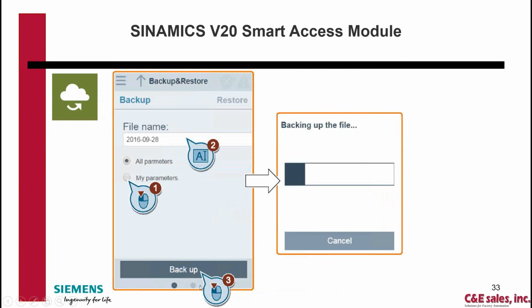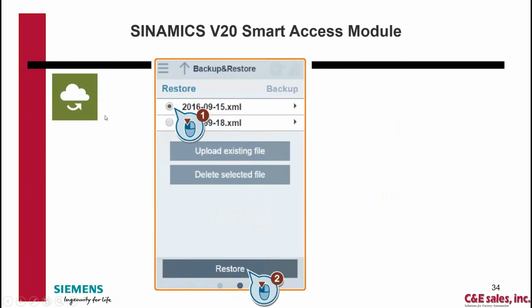So again, on the backup page, you've got 2 dots. Click the 2nd dot. It's going to be your restore. Restore, again, shows you the list of files on the Smart Access module. Then you can upload that existing file to the drive from there. That would be good if you want to replicate the files, or somebody's been playing with parameters and you're not sure how it's set. This would let you go back to something you had stored as a backup.